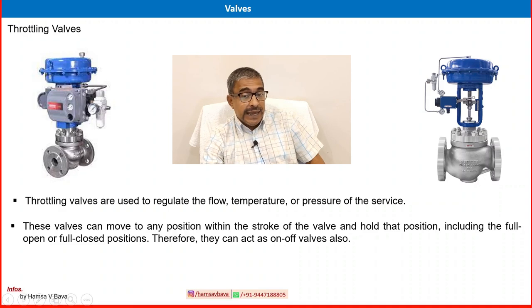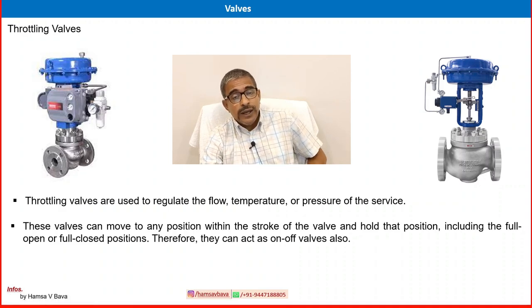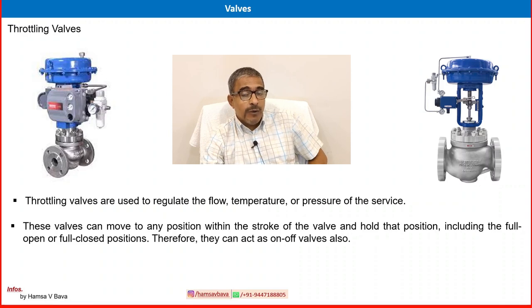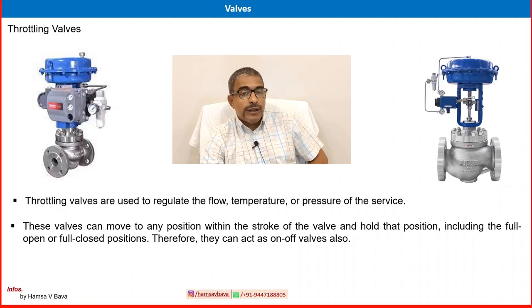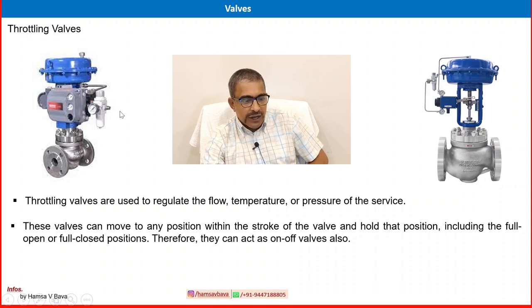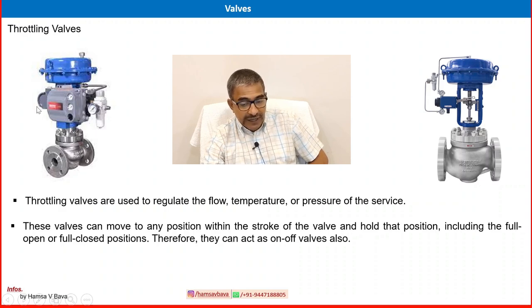Acting as an on-off valve is not the throttling valve's primary function. It normally works anywhere above 0 and below 100 percent open. Its core function is maintaining the flow of fluid to control pressure, temperature, flow, or level. That is why an actuator is present — in this case, a pneumatic actuator. A positioner and pressure regulator are also there, along with an I2P converter. Many items are visible here: the positioner, opening and closing element, and pneumatic actuator system for operating the valve.